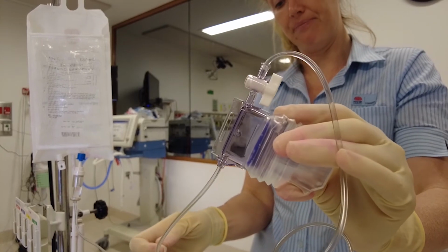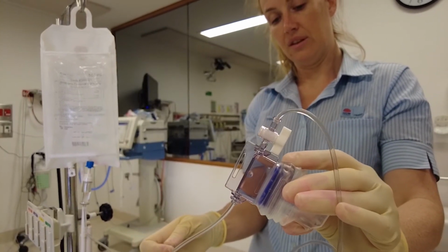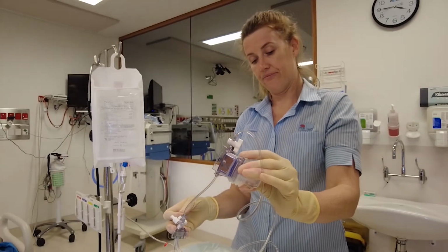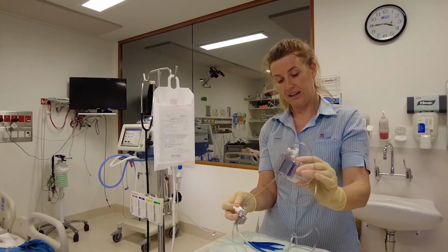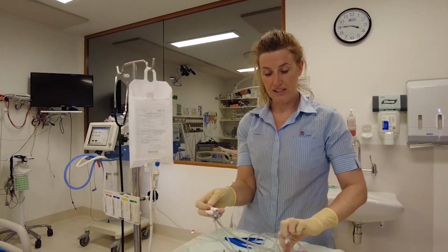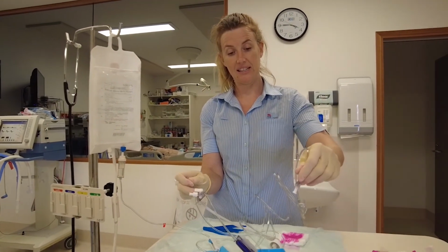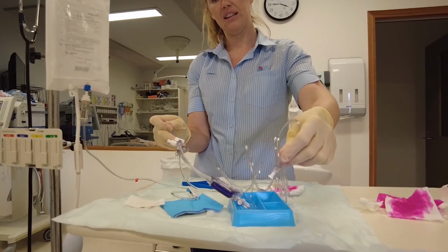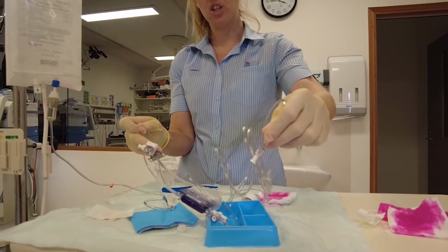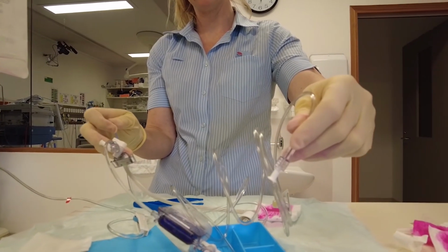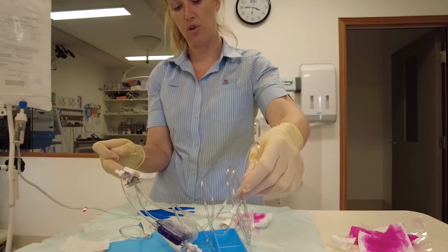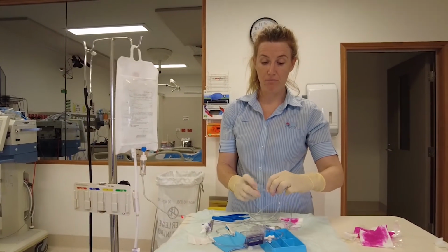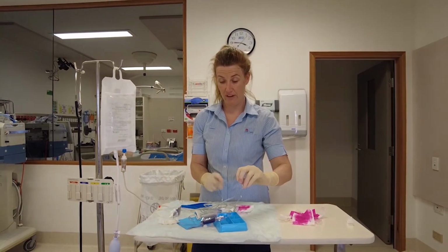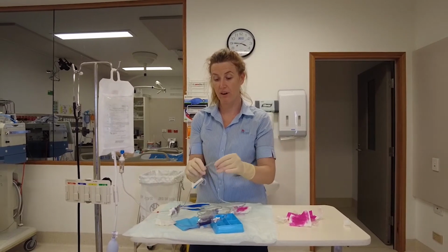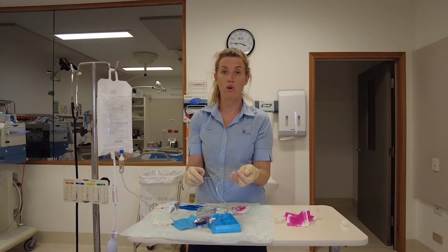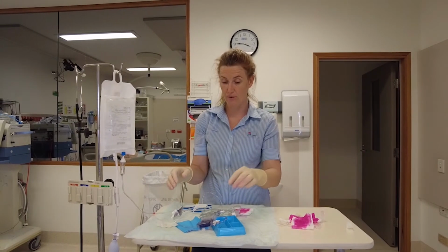I'm going to finish priming my line. Now when I get to the end, I'm just going to point this into my kidney dish so you can see it, but when I get to the end it will prime out through the end. So if you've got air bubbles, you can just keep holding open your fast flush valve or your blue tab, just keep pulling it until you've got all of your air bubbles out. It is really quite important that you go to a great deal of effort to get your air bubbles out, because like I said, that's one of the very first things we want to troubleshoot when we think we've got an inaccurate trace or our damping is an issue.